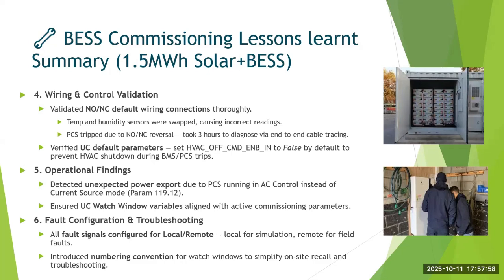So in that case, what was happening is we had wrongly set the default parameter for HVAC, so it was not accepting any commands from our controller. When we started charging, we saw that the temperature was not getting controlled and the cell temperature kept increasing. When we investigated, it was a basic issue in the software: the remote command for HVAC was disabled. So those things have to be properly checked during commissioning. The more detailed a checklist you have, the better it is from the commissioning point of view.